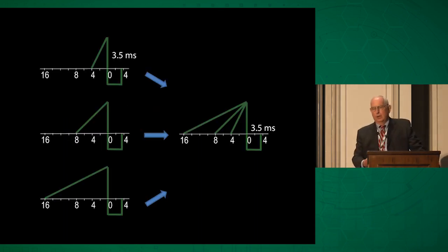We know from theoretical and experimental studies that there are waveforms that are more efficient for defibrillating than a truncated exponential. I mean, you got the truncated exponential because you charge a capacitor and it discharges. It turns out that waveforms in the first phase that do the opposite of that, start at 0 and increase, defibrillate with lower energy.